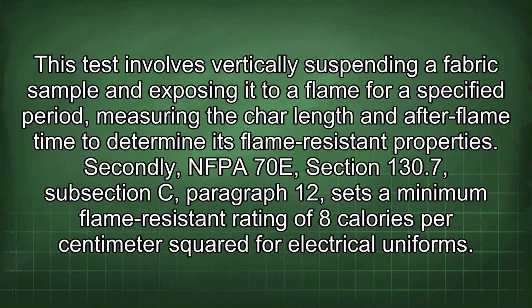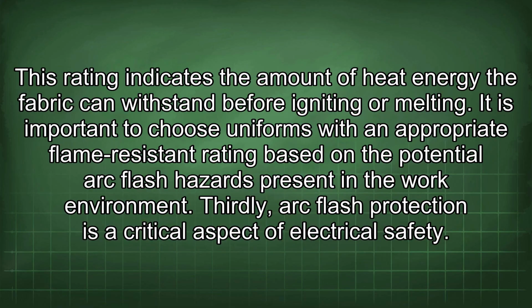Secondly, NFPA 70E, Section 130.7, subsection C, paragraph 12, sets a minimum flame-resistant rating of 8 calories per centimeter squared for electrical uniforms. This rating indicates the amount of heat energy the fabric can withstand before igniting or melting. It is important to choose uniforms with an appropriate flame-resistant rating based on the potential arc flash hazards present in the work environment. Thirdly, arc flash protection is a critical aspect of electrical safety.